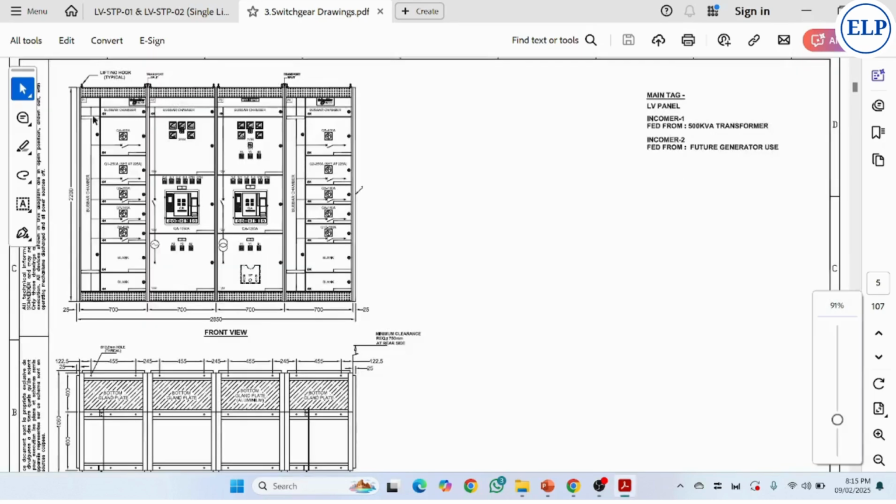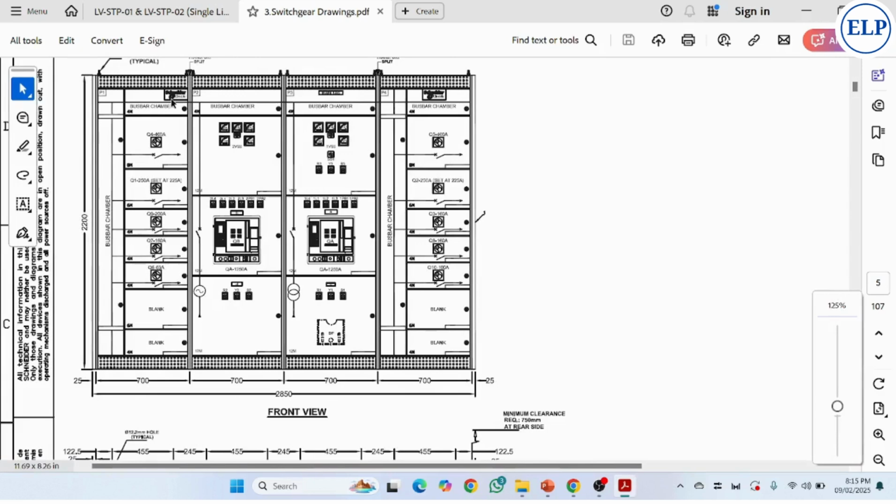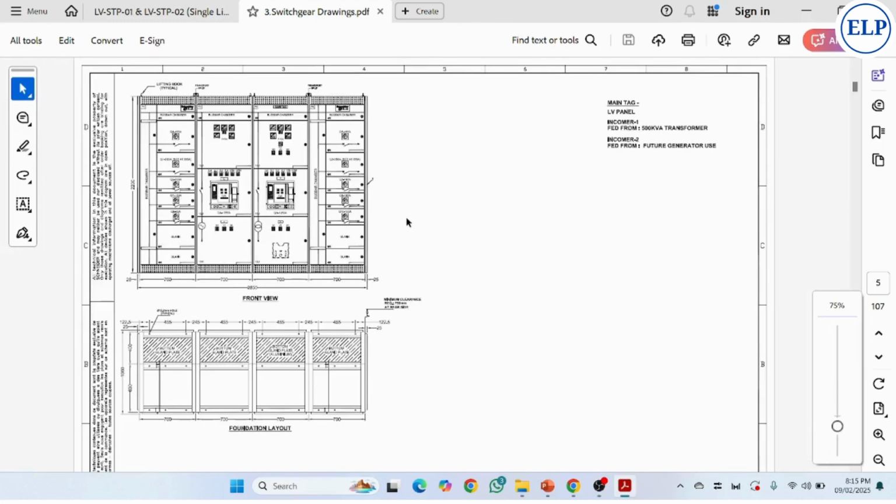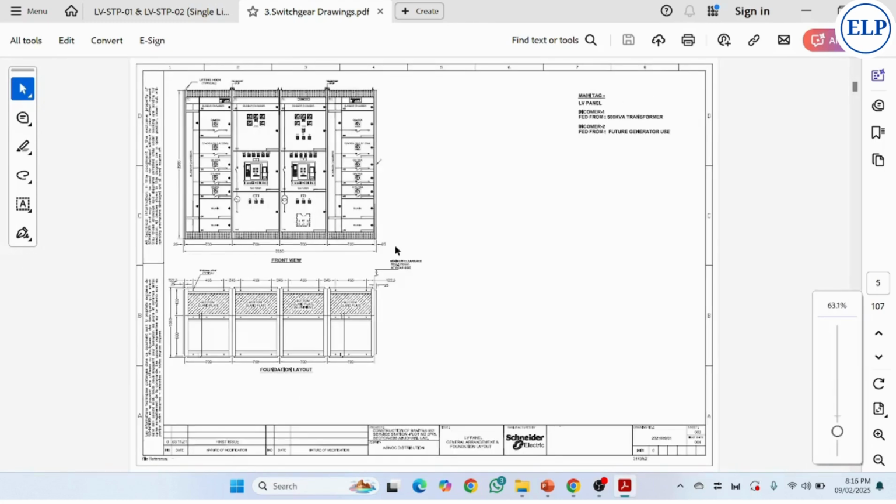We'll see the switchgear panels generally. These we can call cubicles. We'll see incoming source connections with the transformer supply and another cubicle will connect with the generator supply. These are both incomers for the switchgear panel. And we have some outgoing protected devices also, which are connected next continuously to outgoing ended with the loads. Furtherly, we have this, we can call it a general arrangement.